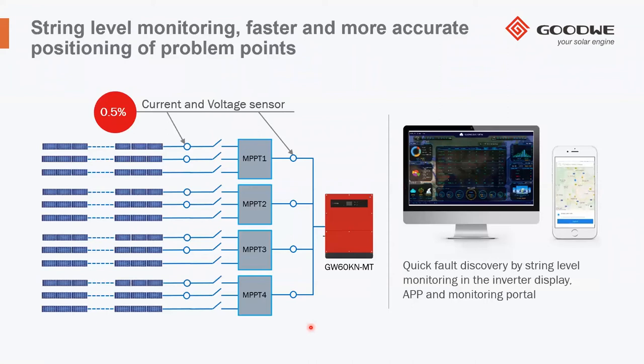Another important feature is the capability of our MT series to have monitoring at the string level. This is extremely important again when performing maintenance, O&M, let's say, because you can easily understand if you have any problem at string level. So you can identify where the problem is and you can just focus your intervention on that string without checking all the rest of the plant.